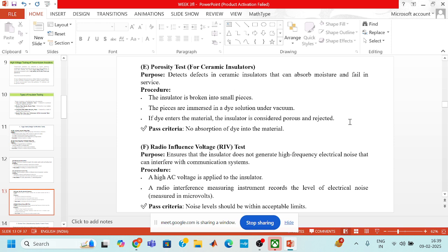Now, last is the radio influence voltage test, also known as the RIV test. It ensures the insulator does not generate high frequency electrical noise that can interfere with the communication system. For this purpose, first of all, we have to apply a high AC voltage to the insulators, and our radio interference measuring instruments record the level of electrical noise. If the noise levels are within acceptable limits, then the insulator will pass the RIV test.